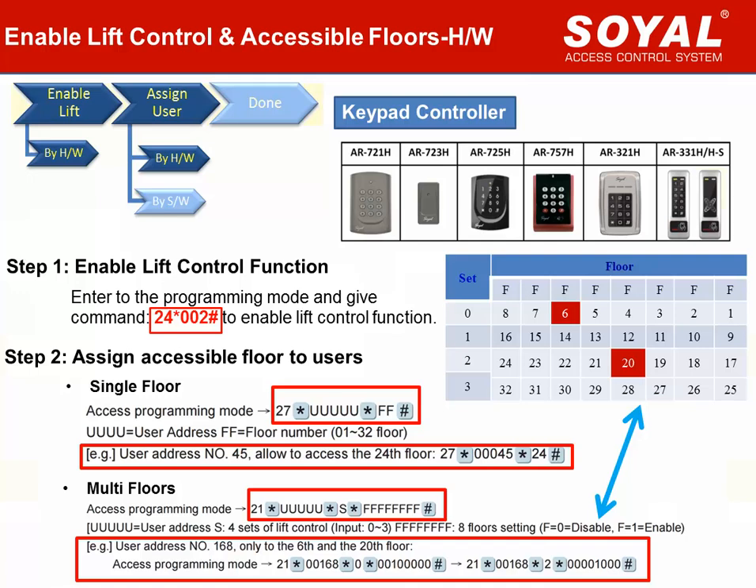This page covers how to use the hardware method to set up the keypad controller. Step 1: Enable lift control function. After entering programming mode, press the key to give command 24 star 002 hash. The controller will then enable lift control function. Step 2: Assign permitted floors for each user card. Command 27 is for single floor setting. For example, user address 45 is permitted to access only floor 24. Press key: 27 star 00045 star 24 hash.